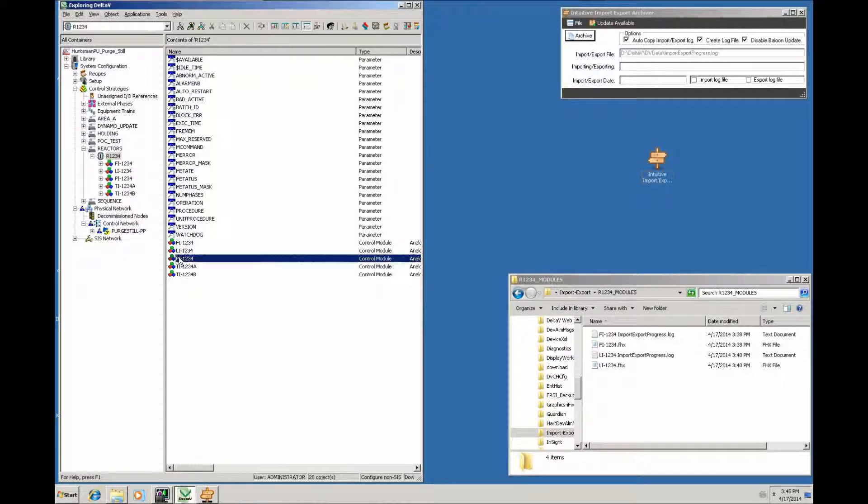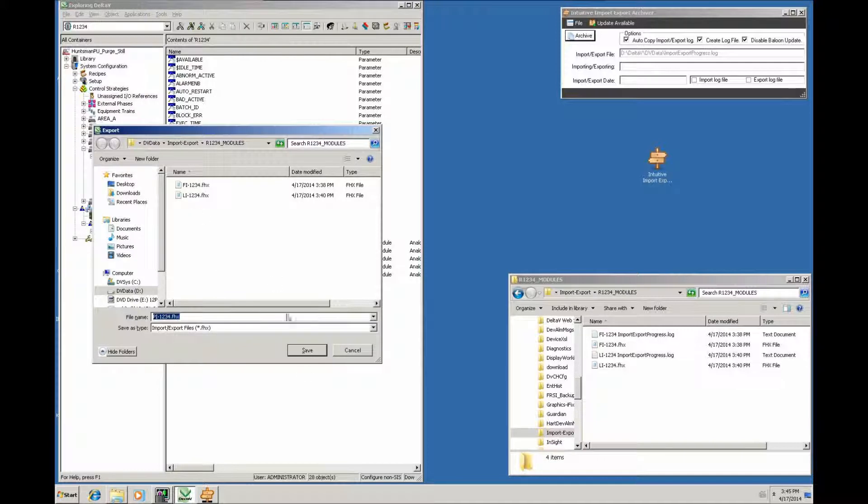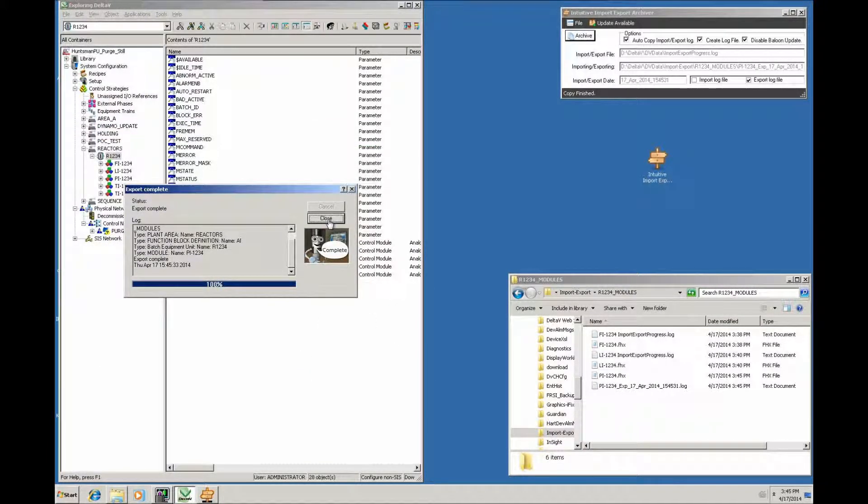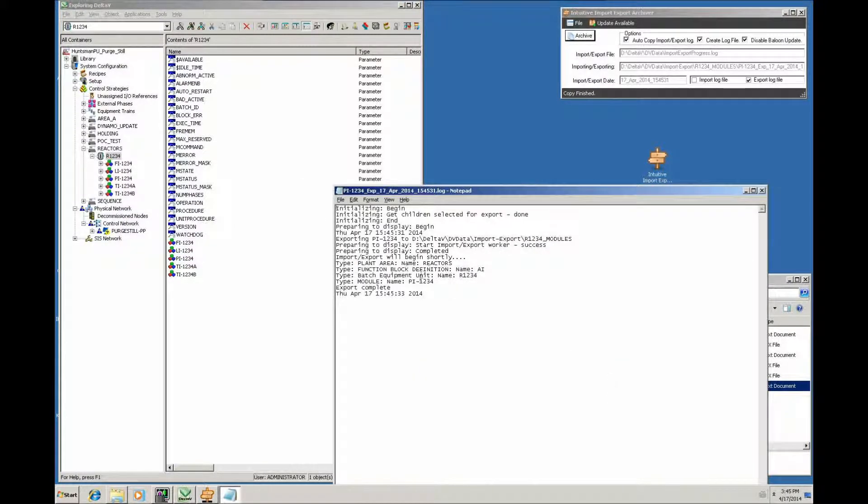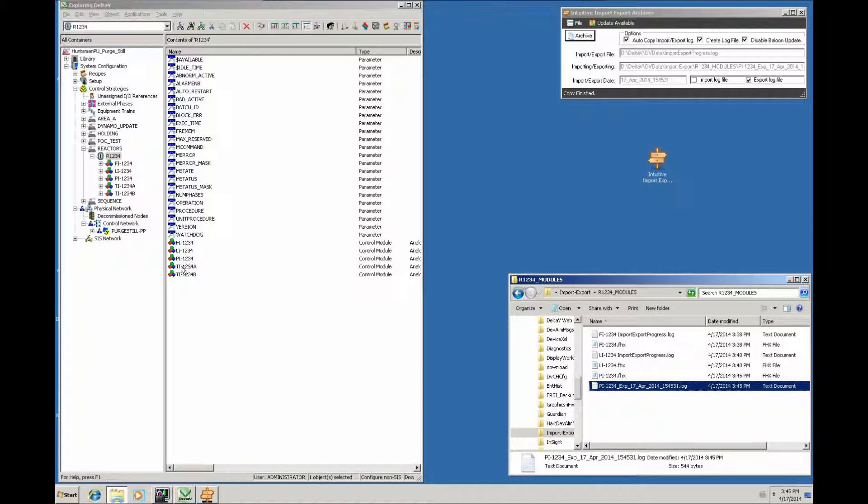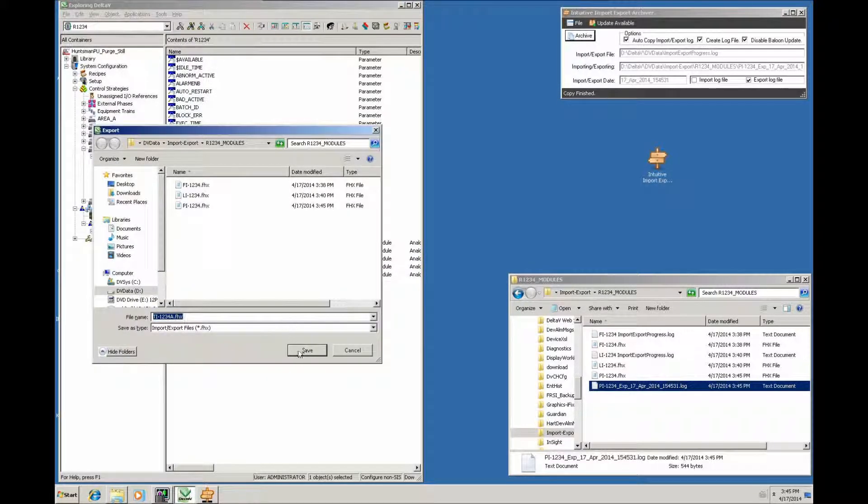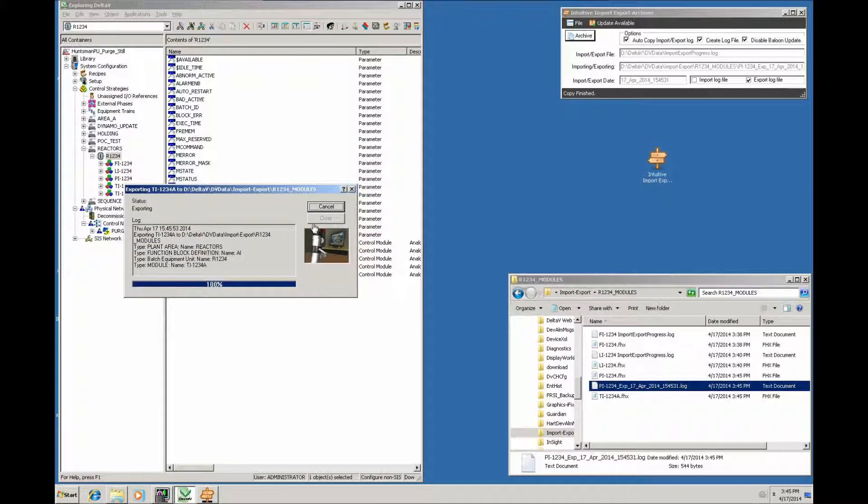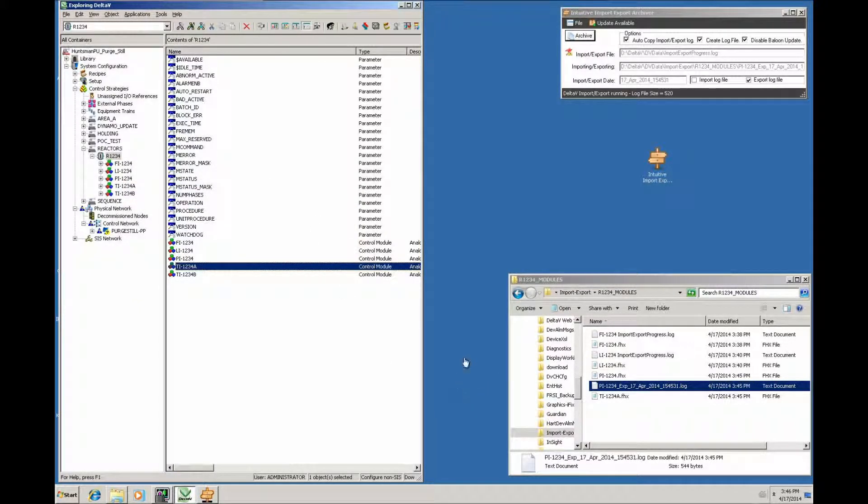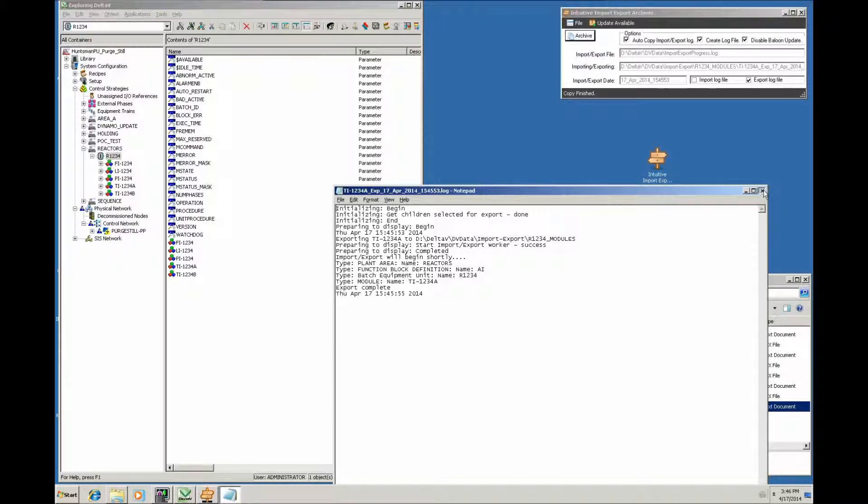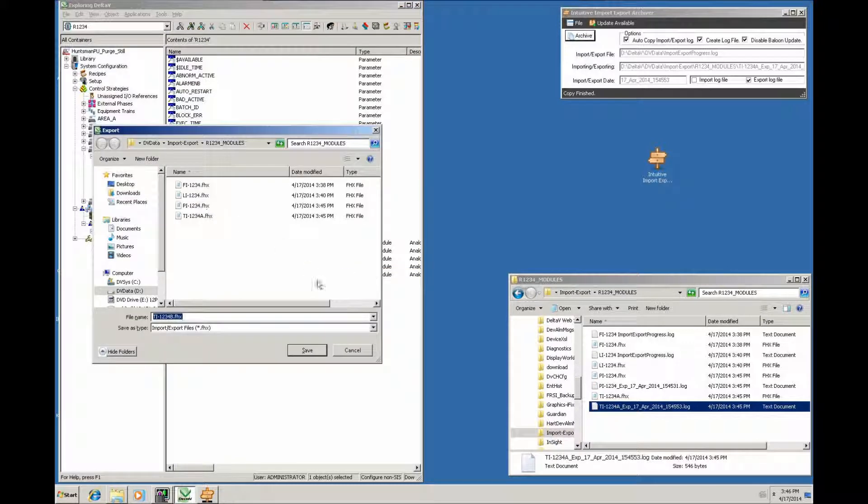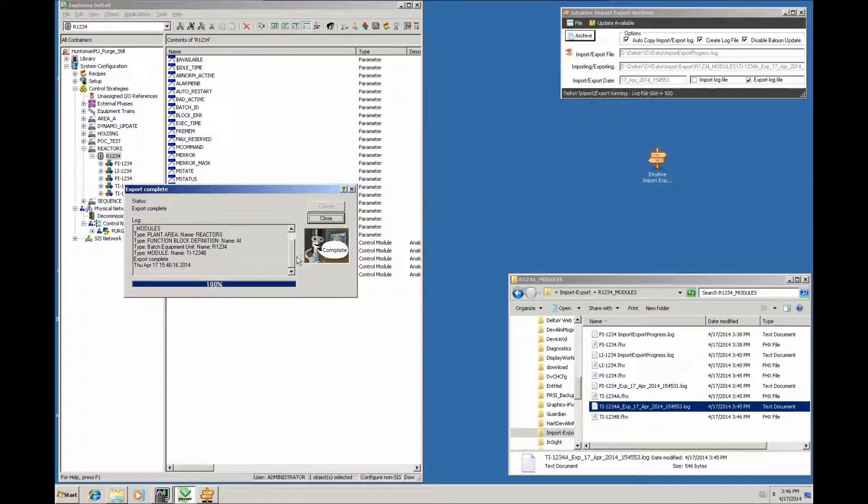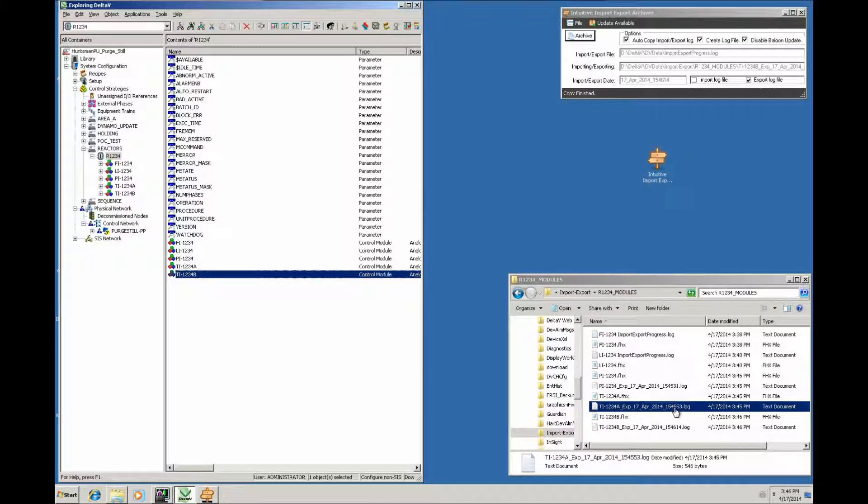If we now perform the export here to the same folder, what you should see is that it's copied across the import export file automatically. It's the one that's just been created, and it's stored it in the location where the FHX file was. We'll do that for the next module, and you should see that appear. For that module, and the same here. We get some statement showing that it's the latest information, that it's an export file, and it shows the date that it was performed.